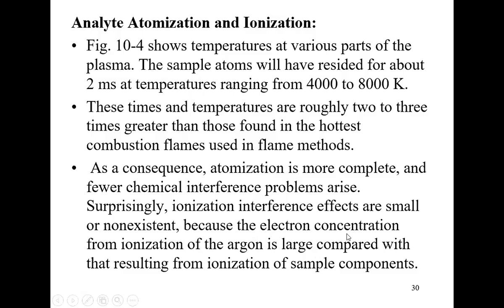So because the electron concentration from ionization of the argon is large compared to that resulting from the ionization of sample components, this large buffer of electrons that is produced from argon shifts the equilibrium to form the atoms to the left, so to say.